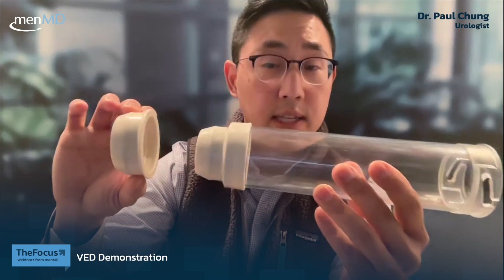This is the penile tube. The pump, which we'll put on shortly, will be attached in this area. You can see that there are grooves in the side, and it will fit into that area and screw on. Once again, in terms of the transfer sleeve, which is here, there are two sizes of transfer sleeves, and as you can see here, there are different girths of the transfer sleeve that you can utilize for your best fit.